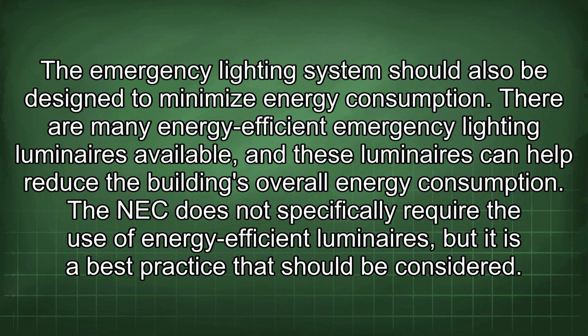The emergency lighting system should also be designed to minimize energy consumption. There are many energy-efficient emergency lighting luminaires available, and these luminaires can help reduce the building's overall energy consumption. The NEC does not specifically require the use of energy-efficient luminaires, but it is a best practice that should be considered.